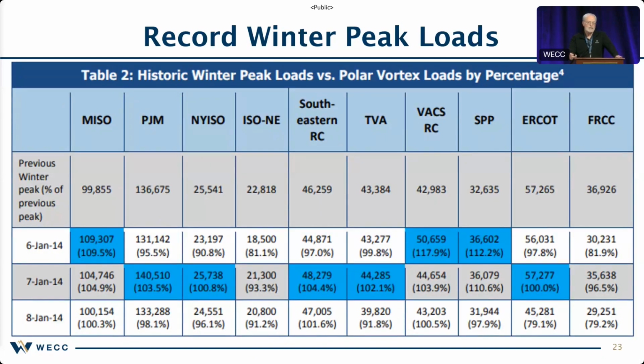So another aspect of these cold weather events that we see often is peak record winter loads. In this particular case, we can see there were 8 different peaks set during the course of this event, and that's just the electric load being served by these utilities peaking during that particular time. We're seeing more of this, I think, perhaps as part of the electrification of the power system. As you put in things like heat pumps, once the temperature drops below the heat pump's ability to function as a heat pump, it goes to resistive heating, kicks up the electricity usage, and balancing authorities need to be aware of that in their footprint to accurately predict their loads.